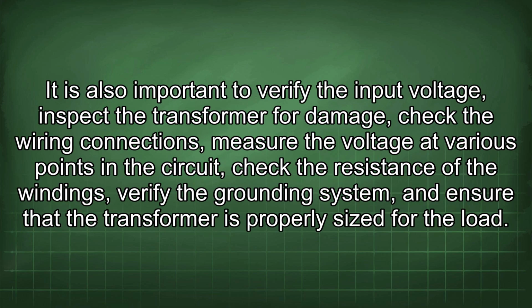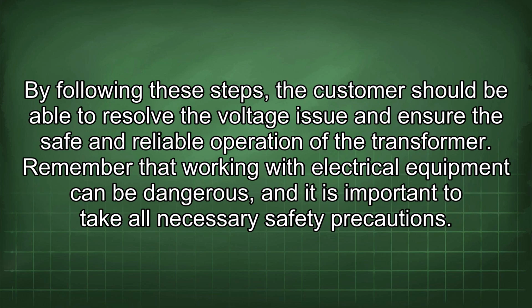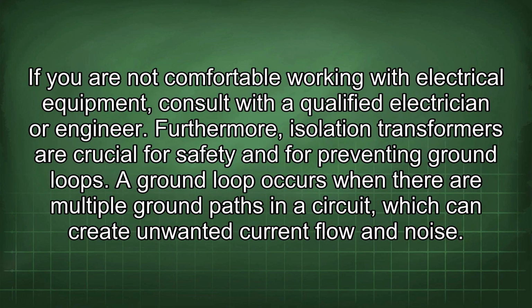It is also important to verify the input voltage, inspect the transformer for damage, check the wiring connections, measure the voltage at various points in the circuit, check the resistance of the windings, verify the grounding system, and ensure that the transformer is properly sized for the load. By following these steps, the customer should be able to resolve the voltage issue and ensure the safe and reliable operation of the transformer. Remember that working with electrical equipment can be dangerous, and it is important to take all necessary safety precautions. If you are not comfortable working with electrical equipment, consult with a qualified electrician or engineer.